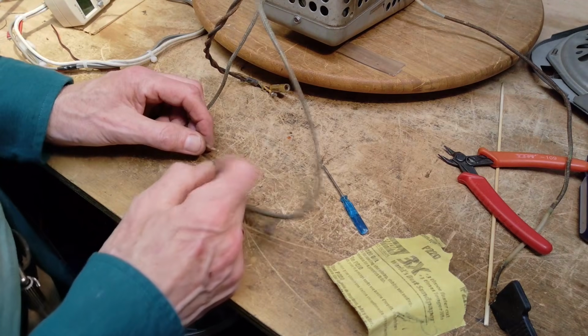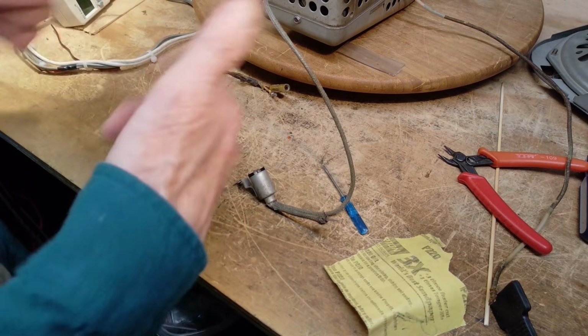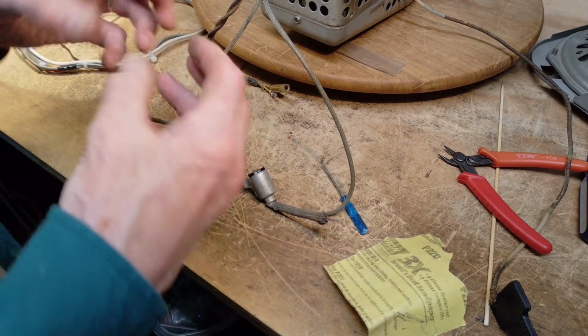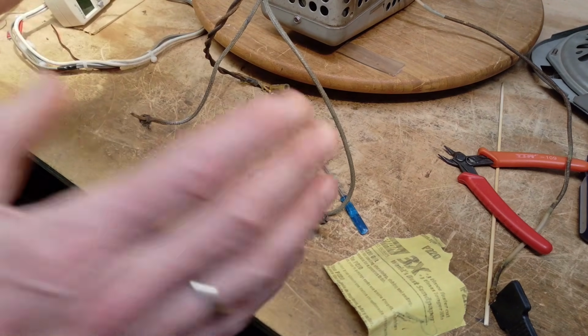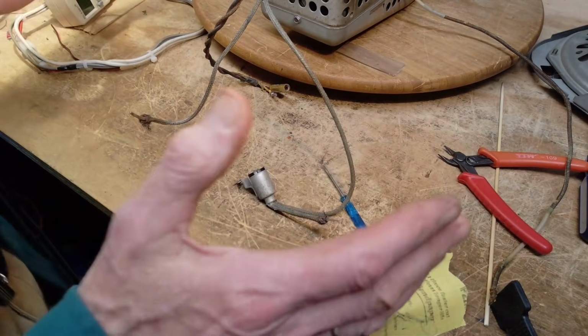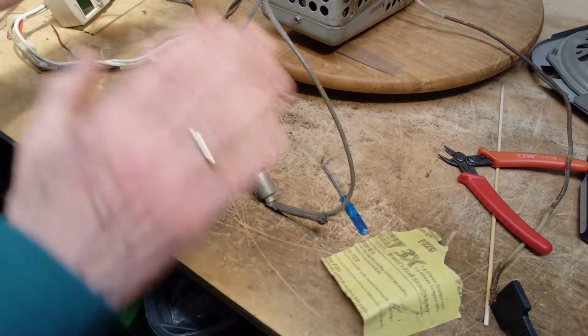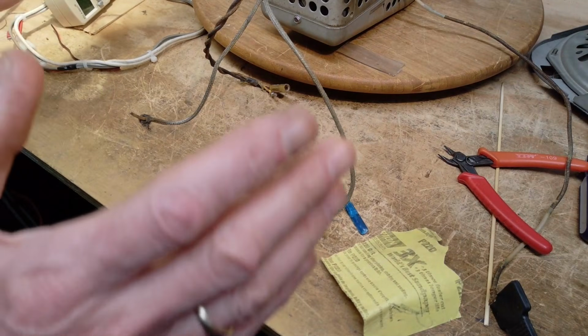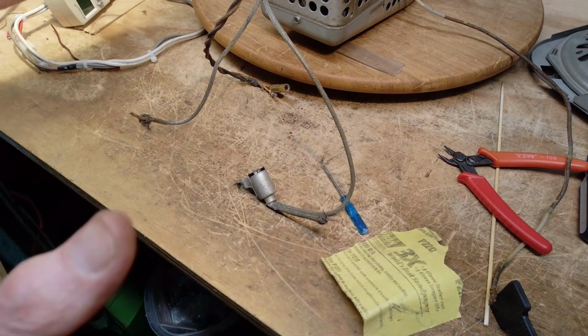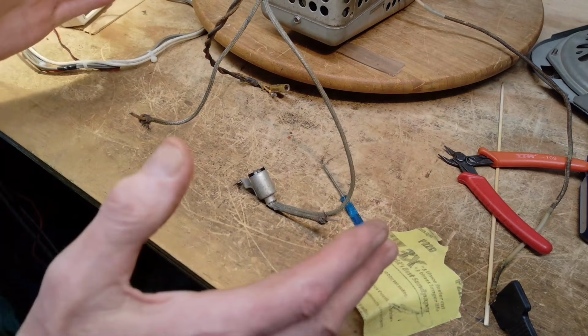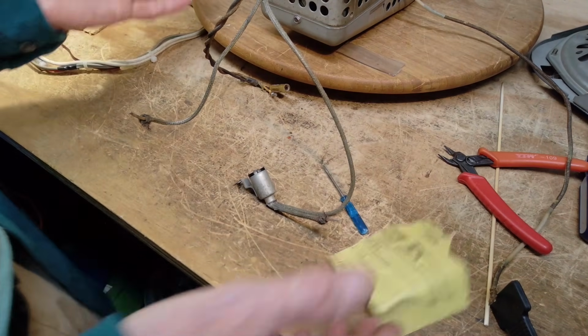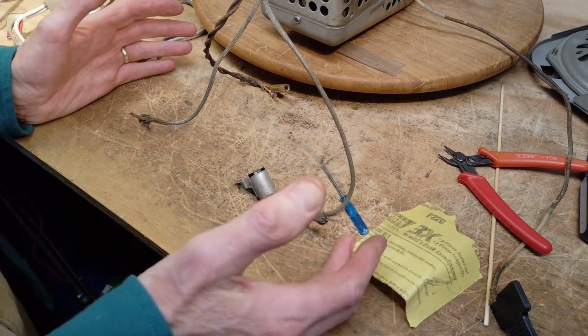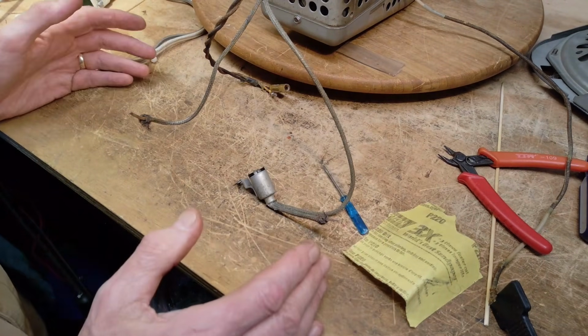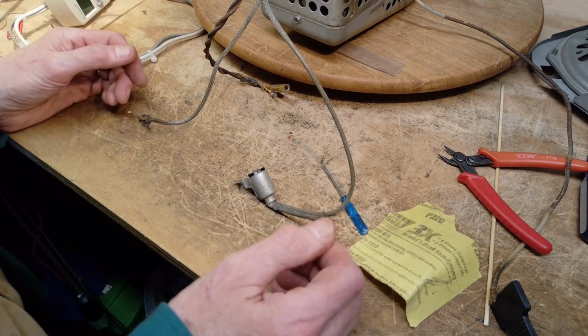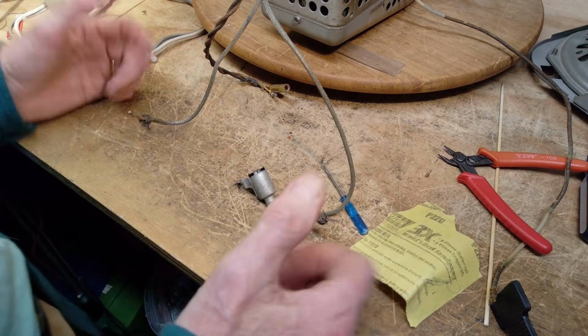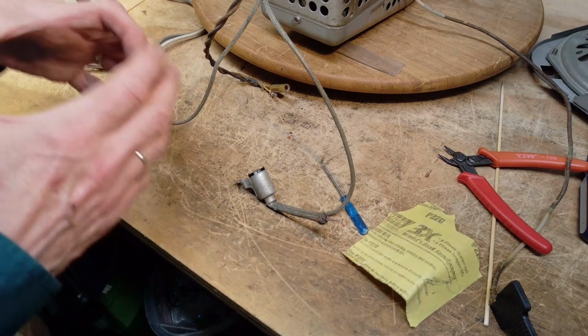The way they get the oil into the paper: they wrap the conductors, so the conductors are insulated with dry paper, and they wrap it onto a great big reel - like those big reels you see on trucks. They do this in the factory, then take it over to where they have a huge tank. You drop this reel in - maybe they do 2 or 3 at a time, I don't know. In goes the reel, then on goes the lid, and they bolt it down so it's vacuum tight. It's a great big thing. Picture a huge reel of cable like that, no lead sheath, just the paper.